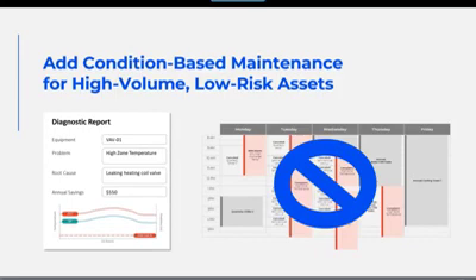That's where FDD can come in and actually run digital checks on this equipment. Look at a VAV box all the time in real time and actually point you to issues as they pop up. So instead of getting a hot call from a particular zone, we can identify months earlier that, hey, the valve isn't really operating properly. You should send someone up there to look at it. It really just drives more impact into a service contract, right? More value out of the services that the controls and mechanical companies are able to provide. So condition-based maintenance for all these low-risk zone pieces of equipment just enables more service to be done.